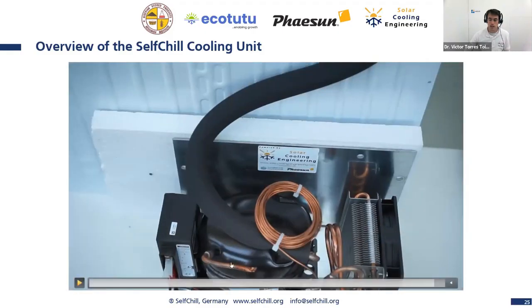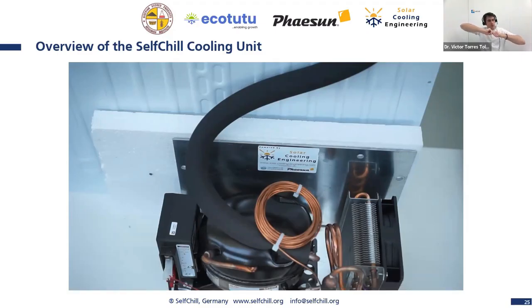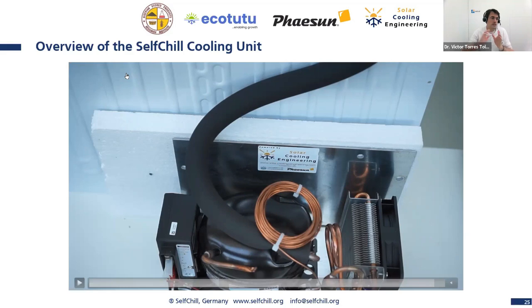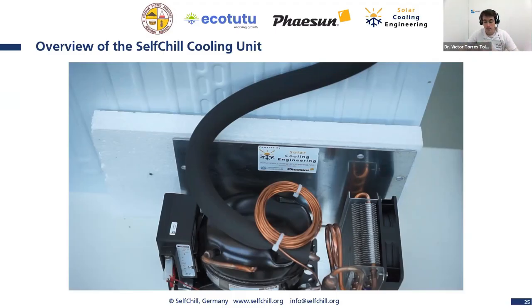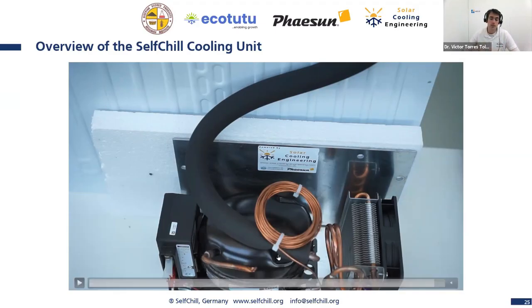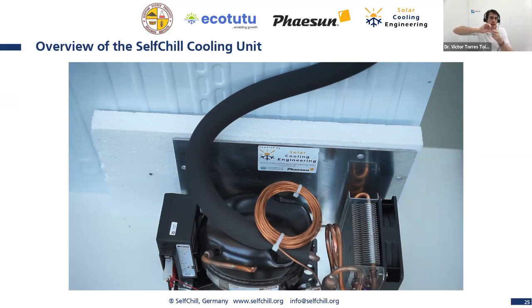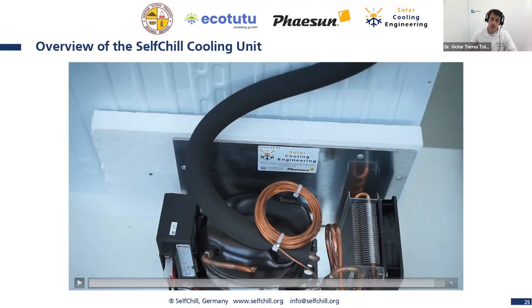Okay, so now we had a look at the different parts. As a review, let me stop the video at this point. Compressor, condenser, the expansion valve is a capillary tube where the liquid goes through and releases pressure, and then the evaporator where this liquid turns into vapor. And now I tell you this machine is controlled by itself. Yeah, the pressures are controlled by itself. Why? If, for example, the condenser is not able to condense the refrigerant, it's because the pressure is not enough to condense the refrigerant. Then we'll have vapor trying to go through the capillary tube, and this is not possible, because with such a long capillary tube you'll have too much pressure drop, so only liquid can go through it. That's why the compressor will keep on compressing until it gets the right pressure, right temperature, so that we get liquid at the condenser. And then when we have liquid, it can go through.